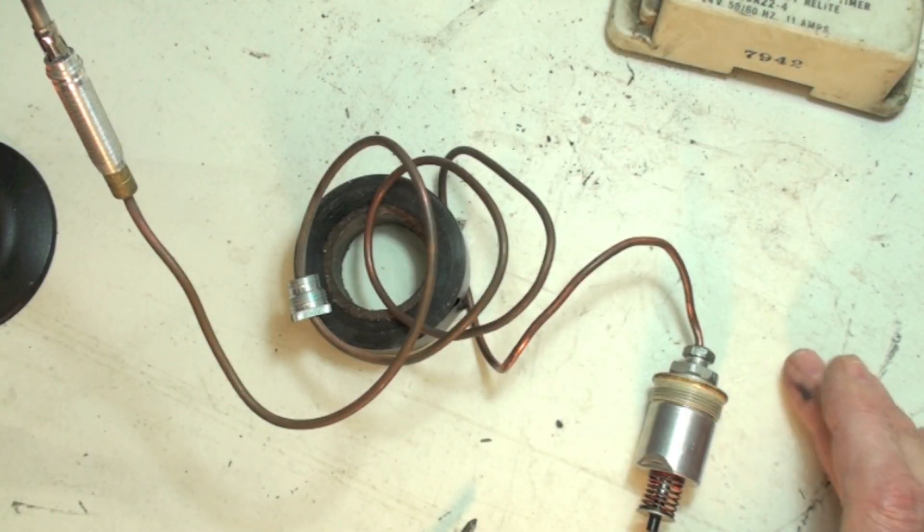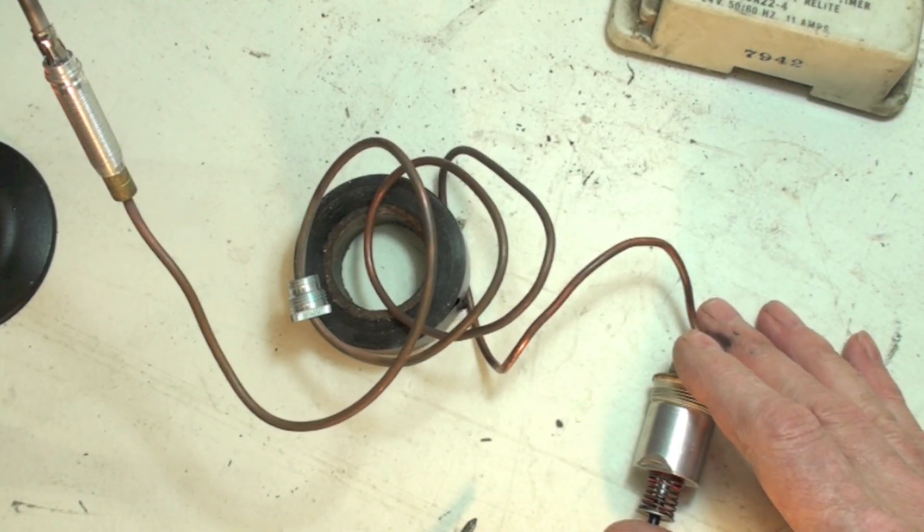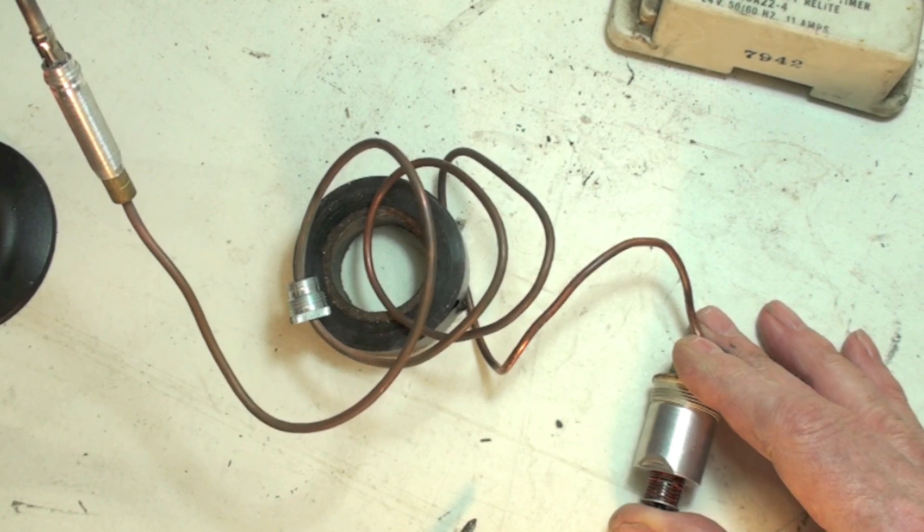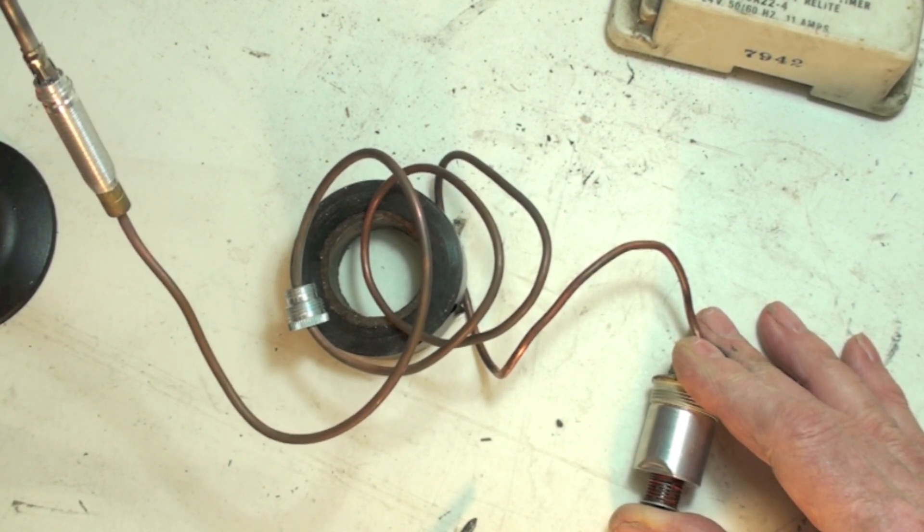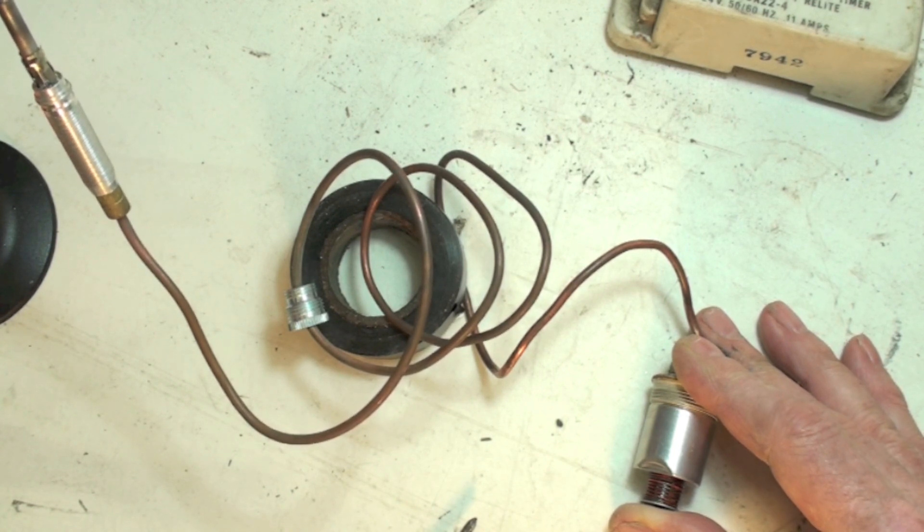When you push your knob on your gas valve to light your pilot, you're pushing this up, and this is actually the flame safety control. This is a little solenoid in here, it's an electric solenoid, and it's operated by the thermocouple.